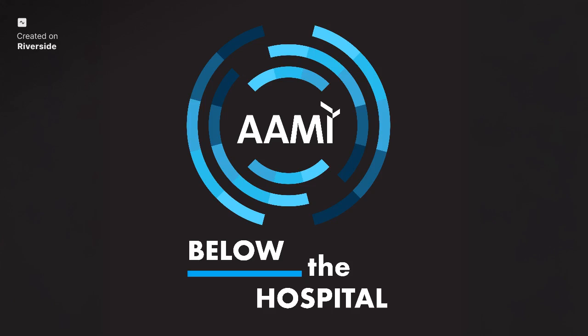But then we also have a new addition to the standard that wasn't there before, and that was ethylene oxide. As you know, ST41 governed the ethylene oxide usage in healthcare practices. It was so outdated that the committee recommended getting that standard into ST58, under low temperature, since it is a chemical and a low temperature sterilization modality. So we have a whole new annex, Annex S, that talks about ethylene oxide sterilization, the updated requirements, the monitoring requirements, and the ventilation systems that you have to have if you're going to be executing this type of sterilization at your facility. Thank you for touching on that, because I did have a question about ethylene oxide, or ETO as folks call it, down the line. But thank you for going there.